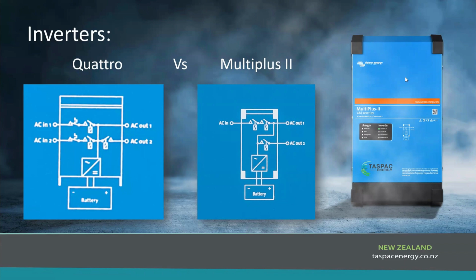Simple. You can also program the AC2 output for a variety of different reasons, which we won't get into the complexity of now, but let's say it's an off-grid system. You can program that to run a hot water cylinder element when the batteries are full. So then it uses the excess solar that's available that normally would just turn off when the batteries get full and just tick over to run the normal loads. Well, if you put a big load on, like a 3 kilowatt element in a hot water cylinder, then that AC2 can be programmed to run that element automatically, giving them hot water, saving them using more gas or whatever.